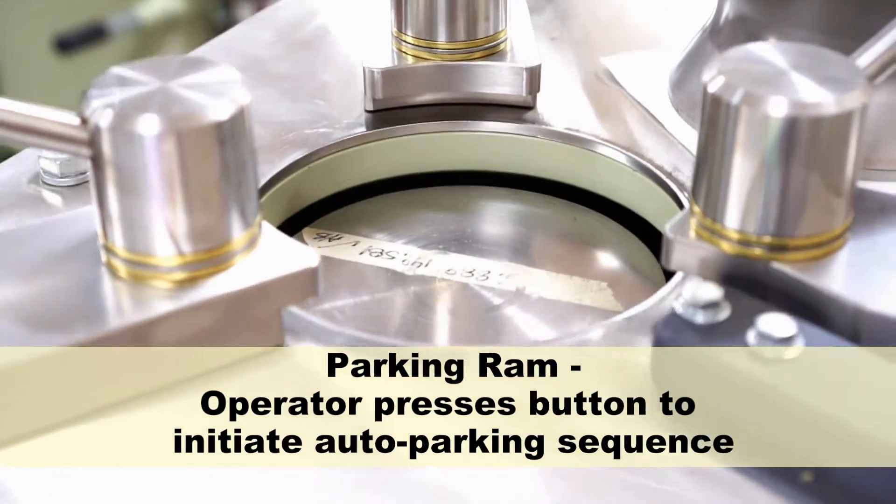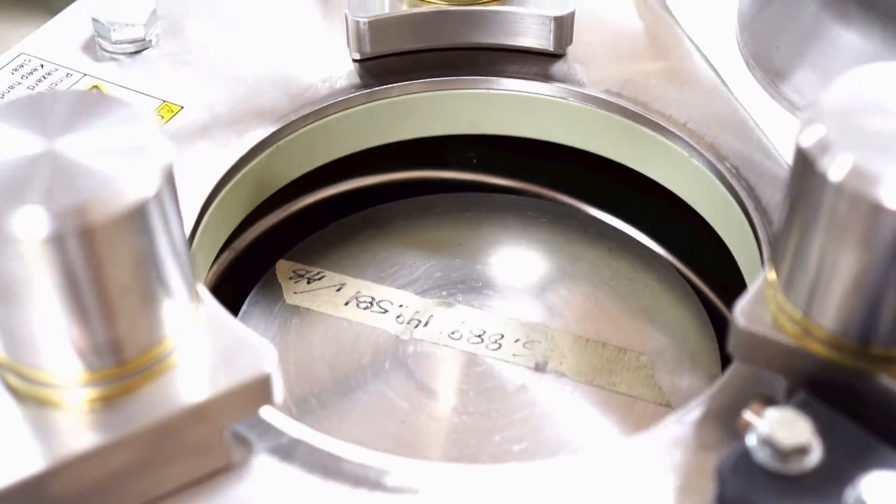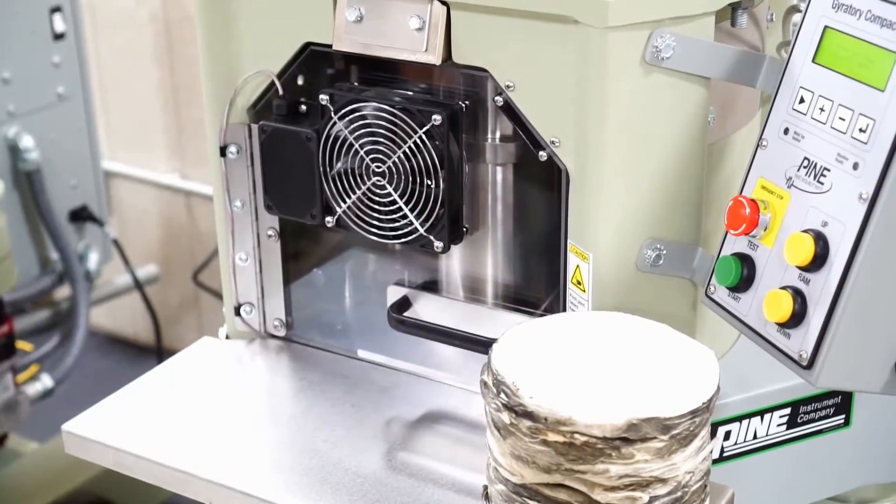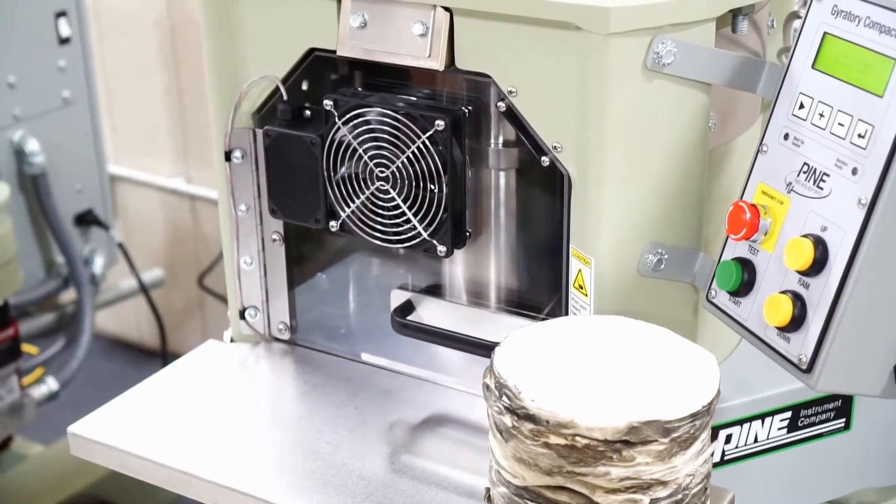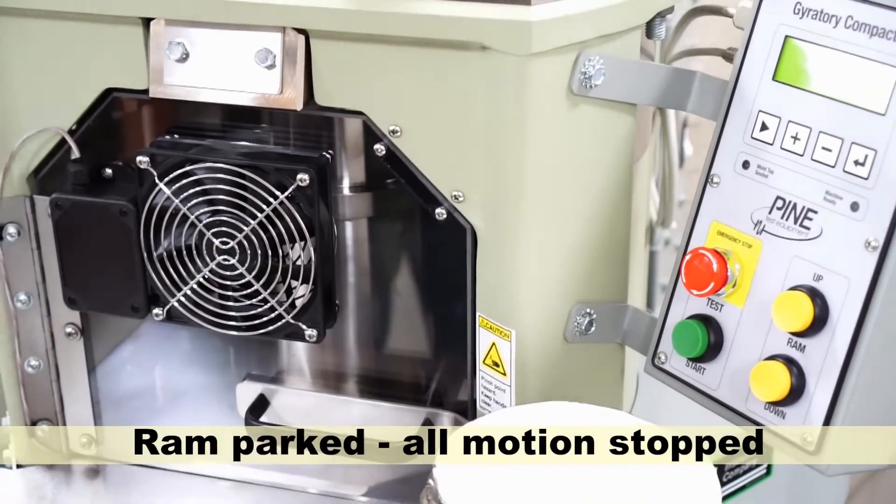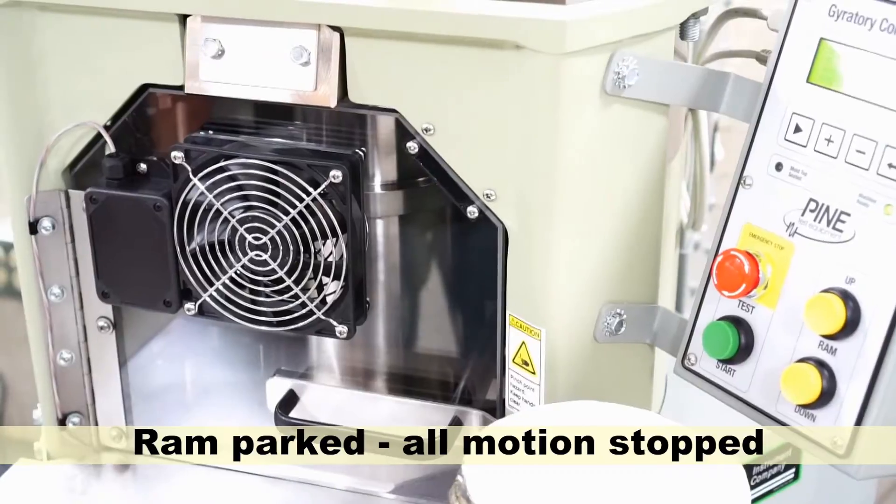The operator then presses either the start or the down button to return the ram to its start position. When the ram is parking, it may be stopped by pressing the e-stop button or by opening the door. When the ram has finished parking, all motion stops automatically.